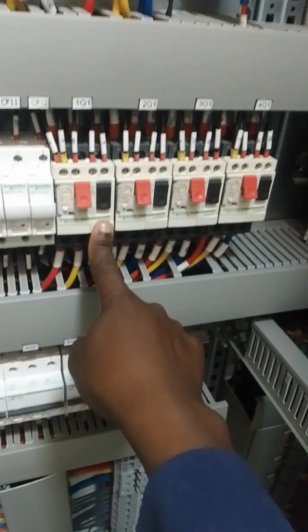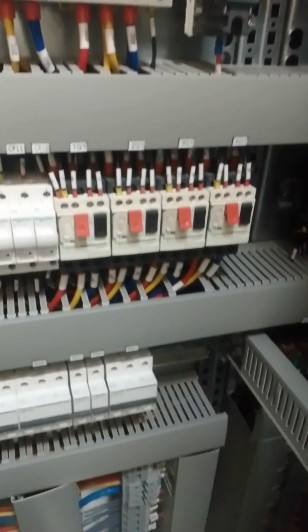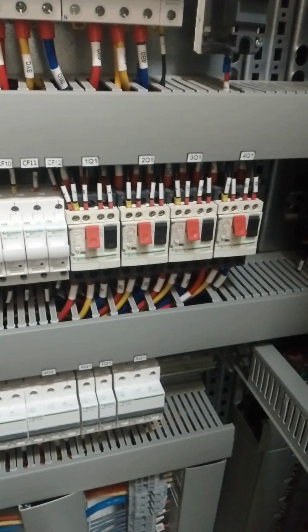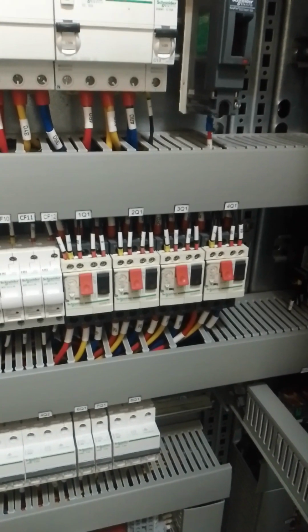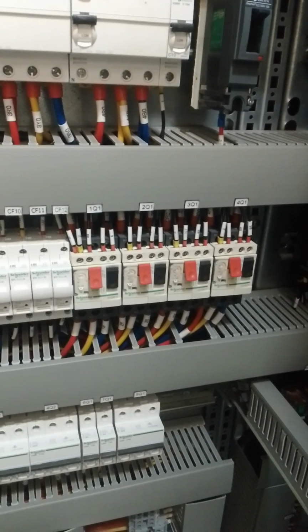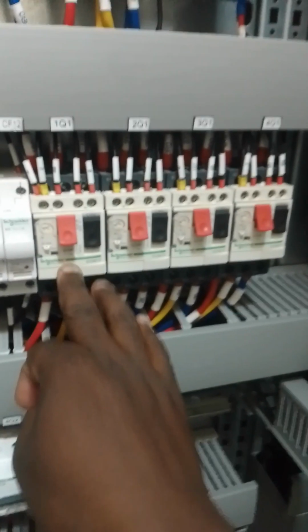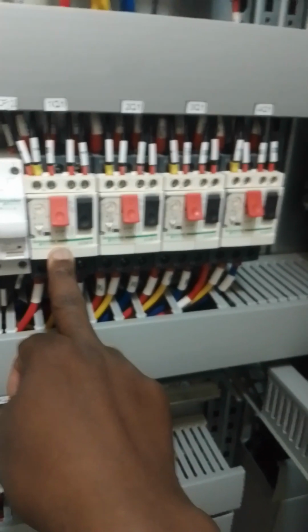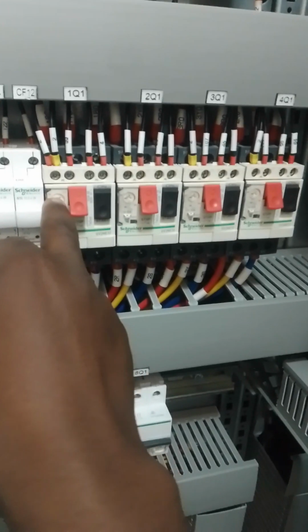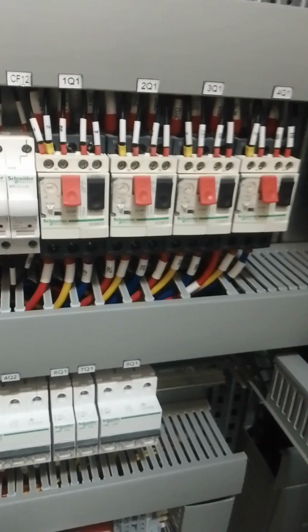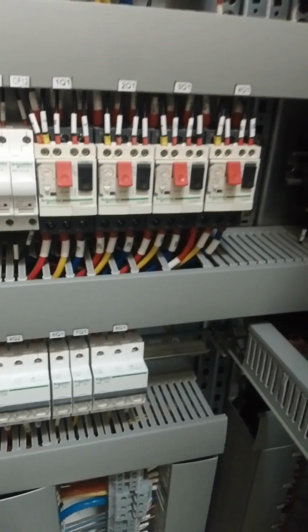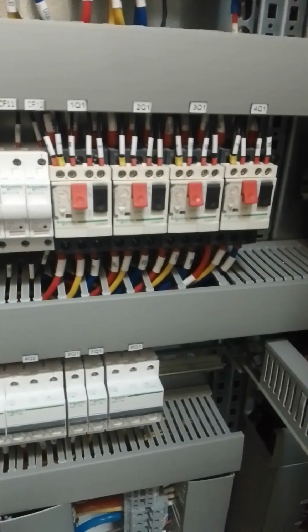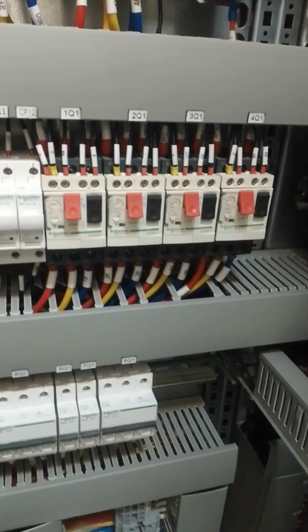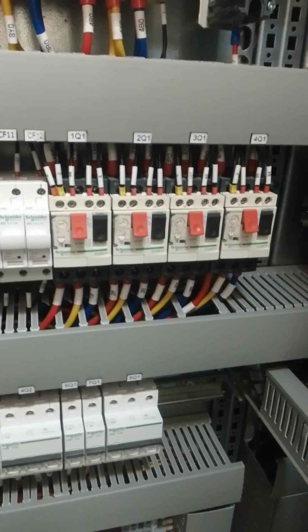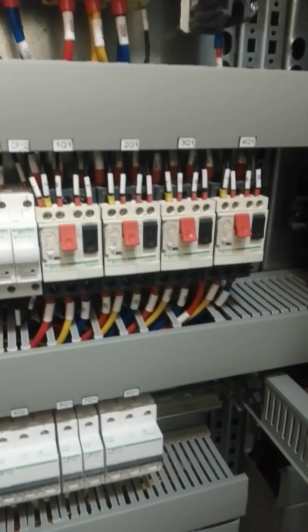This one we call MPCB, motor protection breaker. Its work is to protect the motor when there is high voltage or more demand from the load. This works like a thermal overload also, because it switches off. As you can see, there is a setting you can adjust so it will automatically switch off the circuit when there is any overload or when the motor is overheating.